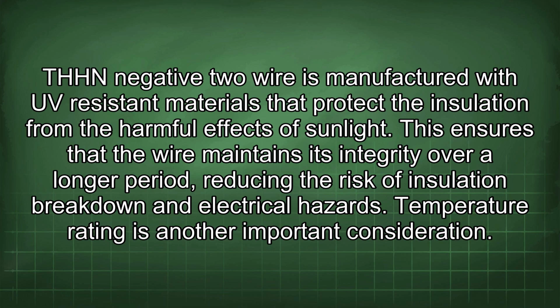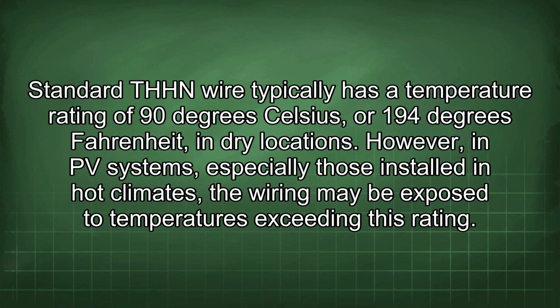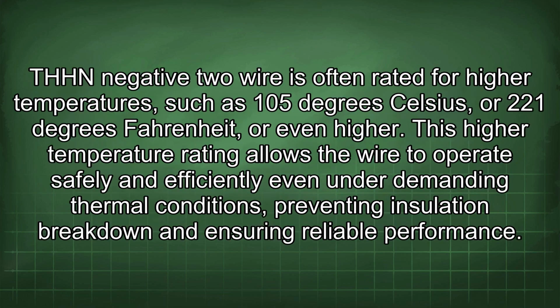Temperature rating is another important consideration. Standard THHN wire typically has a temperature rating of 90 degrees Celsius or 194 degrees Fahrenheit in dry locations. However, in PV systems, especially those installed in hot climates, the wiring may be exposed to temperatures exceeding this rating. THHN-2 wire is often rated for higher temperatures such as 105 degrees Celsius or 221 degrees Fahrenheit, or even higher. This high temperature rating allows the wire to operate safely and efficiently even under demanding thermal conditions, preventing insulation breakdown and ensuring reliable performance.